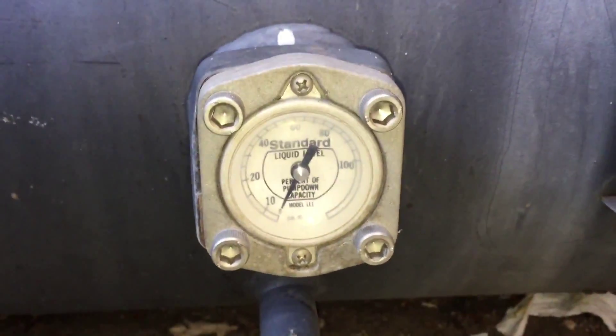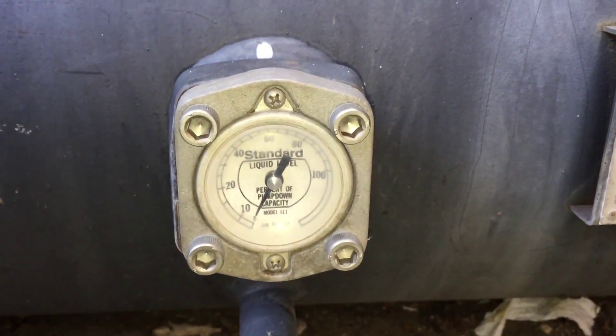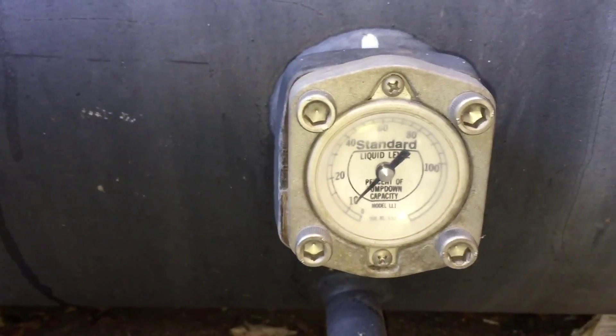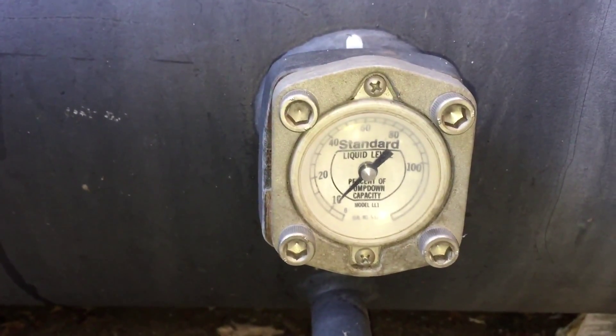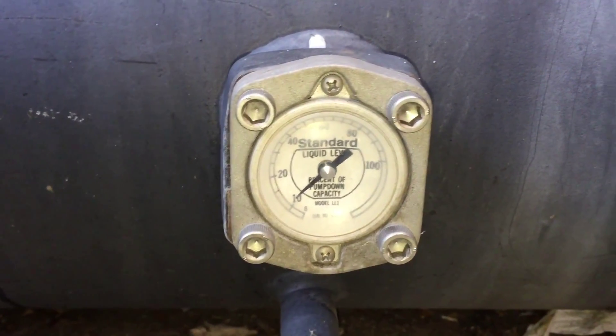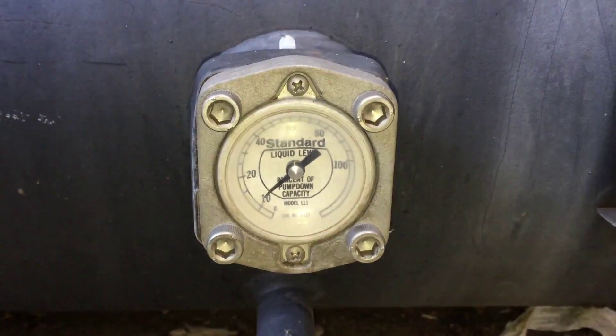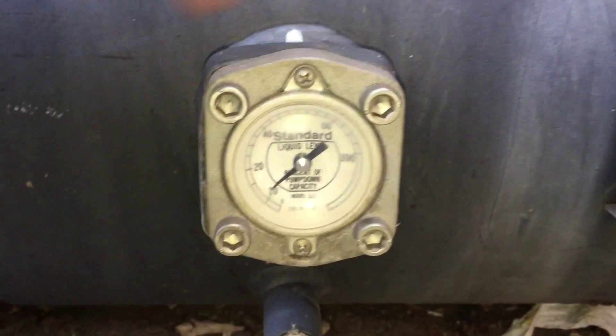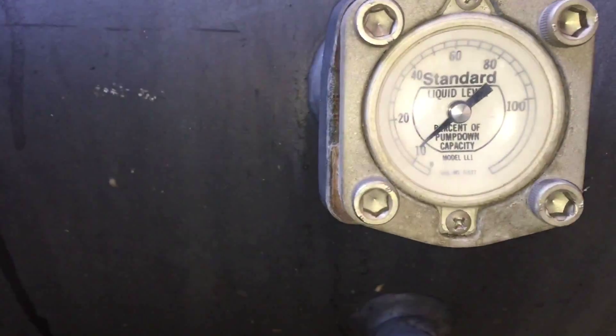So yeah, if you ever see one of these, don't think of it as pressure — I probably thought it was pressure on my first story because I didn't read it. Look, you can see it now just jumping up — up to 10%, so it's doing some work. So yeah, if you see one of these things, firstly read the label: liquid level, which tells you the capacity.